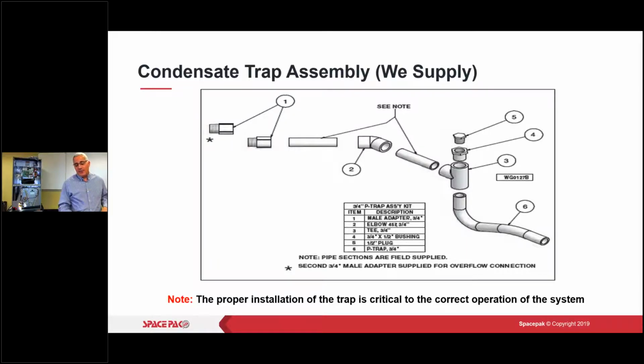If this is not right, what we have seen is the motor, the fan, is powerful enough to actually pull up that condensate and basically blow it all through the cabinet. So if you show up to a job and there's all kinds of rust in the cabinet and a lot of water, it's probably the issue right here with this condensate trap. It's not to our specifications and it needs to be. So don't skimp here. This is very, very important.